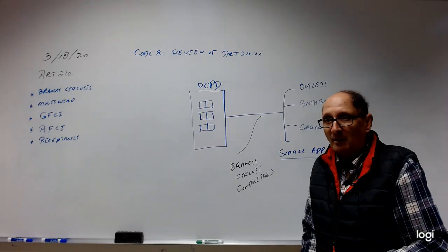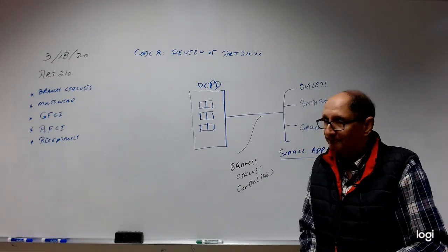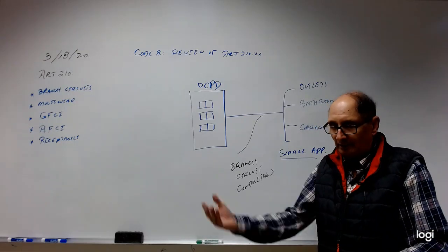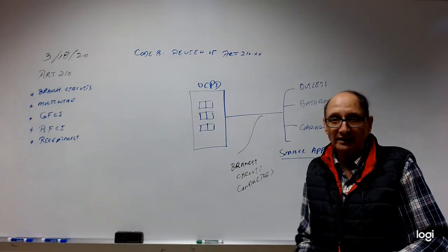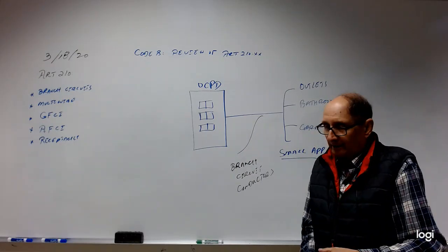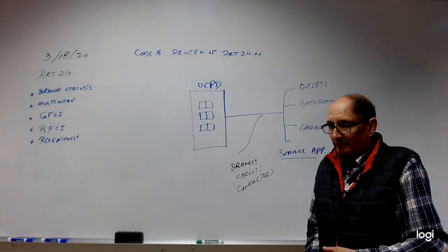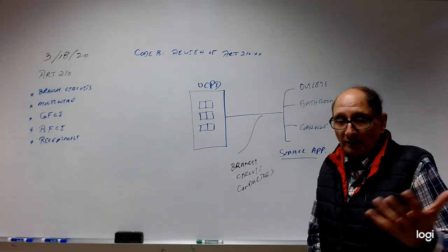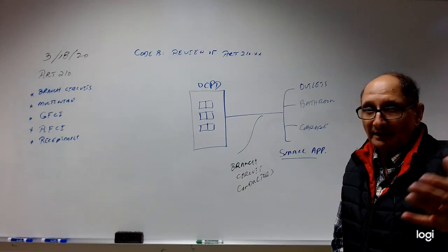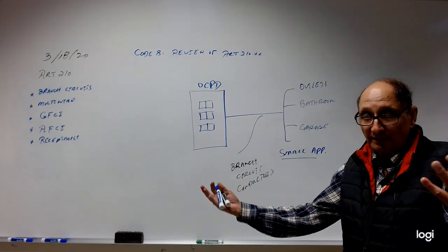Outdoors, you need a minimum of 2 receptacles, front and back. And when it comes to garages, each carport needs 1 receptacle. And for hallways, you are required to have 1 as long as the hallway is a minimum of 10 feet long.